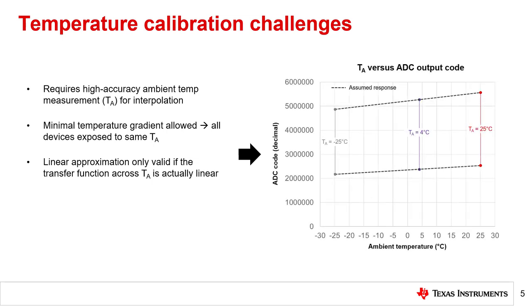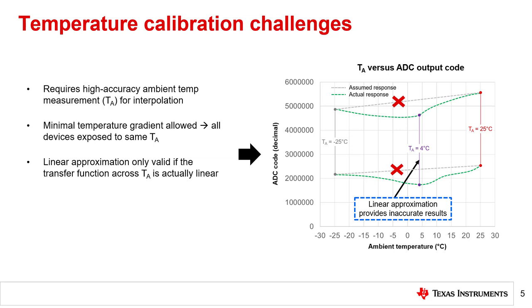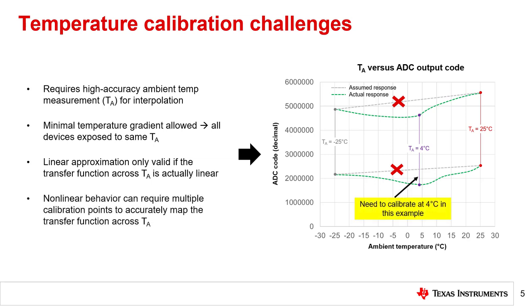The most important challenge with this calibration method is that it relies entirely on the assumption that the error across temperature is linear. However, it is possible that the error between the calibration points is non-linear. For example, if the system actually had a response given by the green dotted lines, a linear approximation between negative 25 degrees Celsius and 25 degrees Celsius would not allow accurate determination of the system behavior at 4 degrees Celsius. Under these circumstances, it is necessary to calibrate at additional temperatures to accurately map the transfer function across ambient temperature. Choosing multiple equally spaced calibration points and limiting the ambient temperature range can help improve the calibrated results and reduce the temperature error.